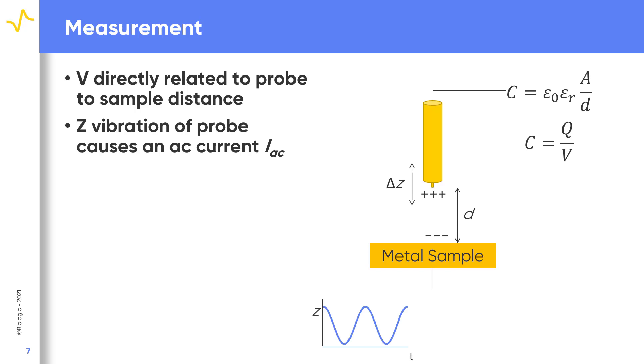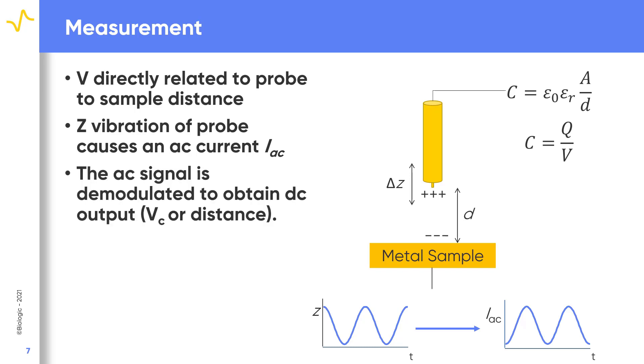In an SKP experiment, the probe is vibrated in Z perpendicular to the sample, changing the probe-to-sample distance. This in turn causes an AC current to form. In the Kelvin probe measurements, a DC signal — either contact potential difference for SKP, or probe-to-sample distance for topography measurements — is of interest. The AC signal is therefore demodulated to obtain the final DC signal of interest.